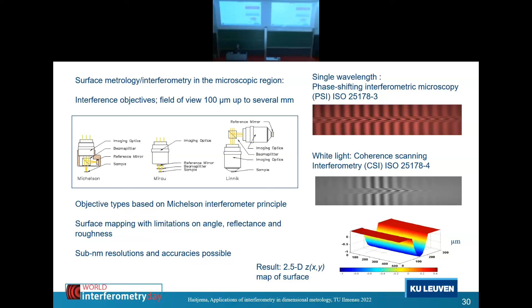And the daily work in the dimensional metrology lab: is there any interferometry around? Even if you have just a box of gauge blocks, you do everything with it. Yes, in every dimensional laboratory, you see that the flatness of gauge blocks is checked with the optical flat. And if you look here, if you need eyeglasses or not, we still have to discuss. But okay, if you look here, you see fringes, and from those fringes, you can see if the gauge block is flat or not. And I don't know where my example is.